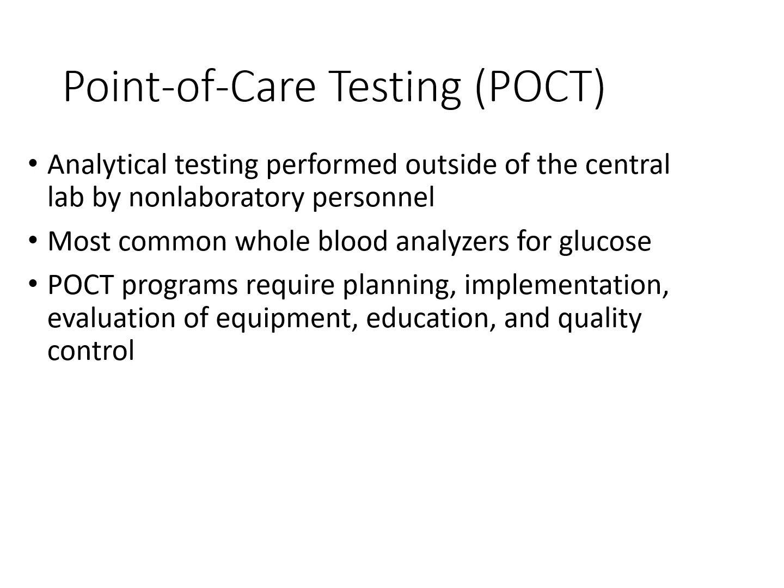A point of care testing program is going to require planning, instrumentation, evaluation of the equipment, and continual education for these patient care centers. There's a lot of turnover a lot of times in the staff that are doing the point of care testing. Typically they're not laboratory personnel, and they need to understand that quality control has to be run and found acceptable before they're reporting patient results.